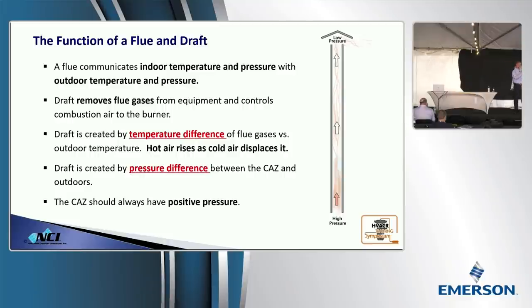Draft. This was really important. If you guys are taking notes, I need you to write this one down. There's very few things I'm going to recommend you write down. This is one that you need to write down. Draft is the force that controls combustion air. It's that second bullet point up there. Draft is the force that controls combustion air. As we start to look at these influencers, we're going to see how they influence draft. Because as draft changes, so does combustion air. That's a relationship I want you guys to take out of this.